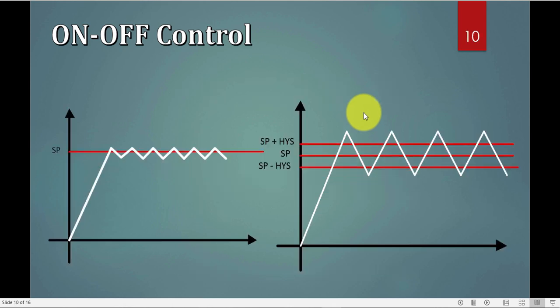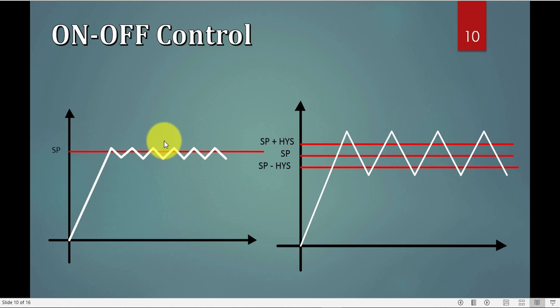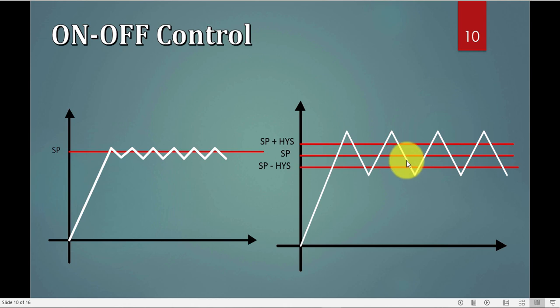Just to have a comparison between both of them, you can see how there are more frequency of on-off in this side, no hysteresis, so it's really to relieve the actuator, we use hysteresis with it. They use this a lot in temperature control, because the heater can take this stress, and it's cheap, it's cheaper than the other method.